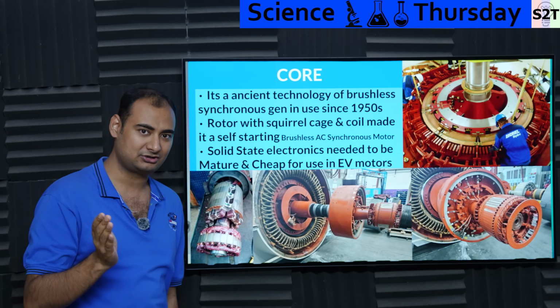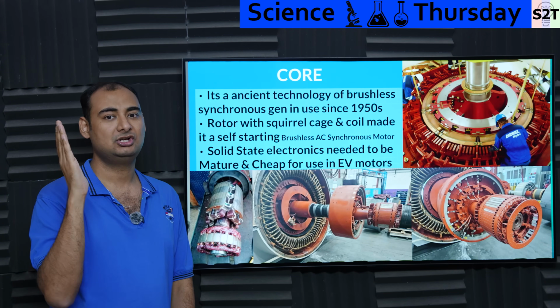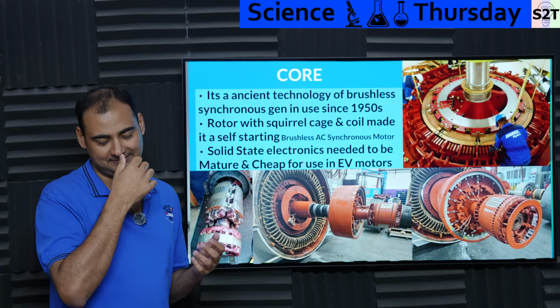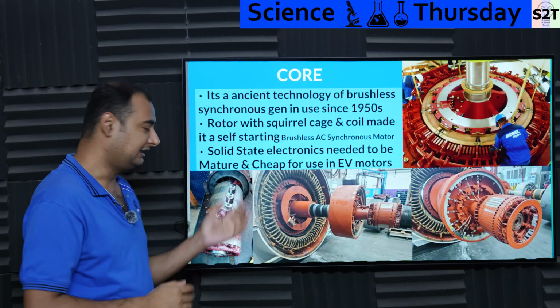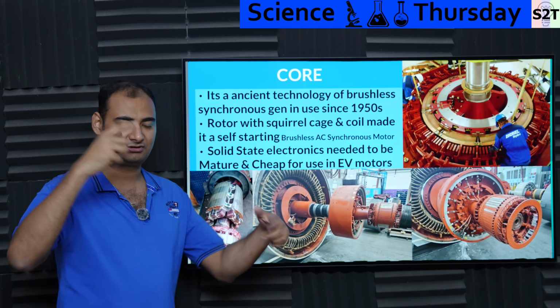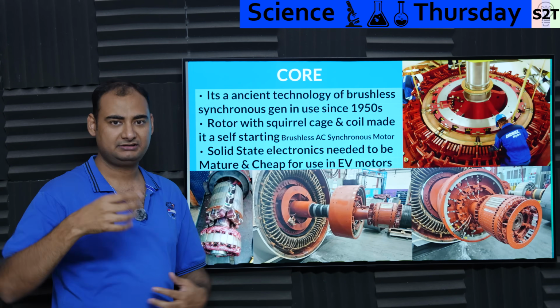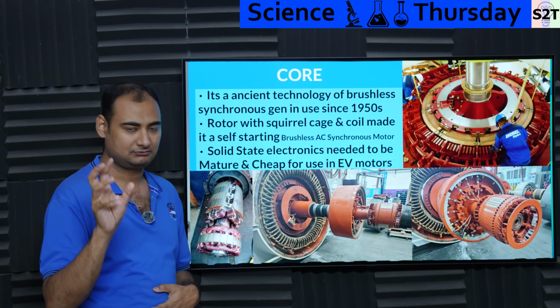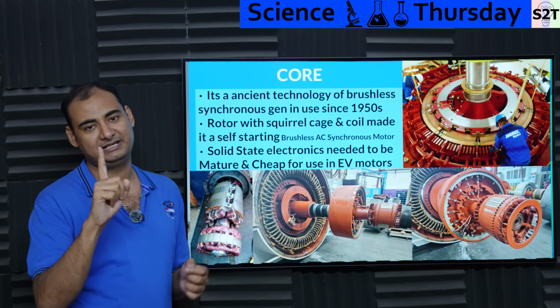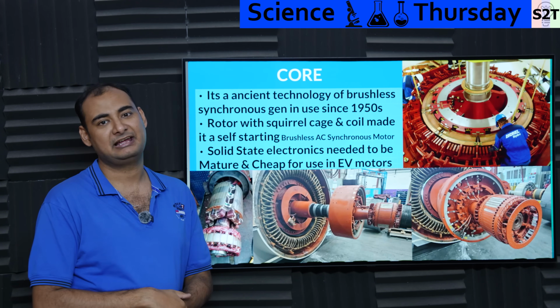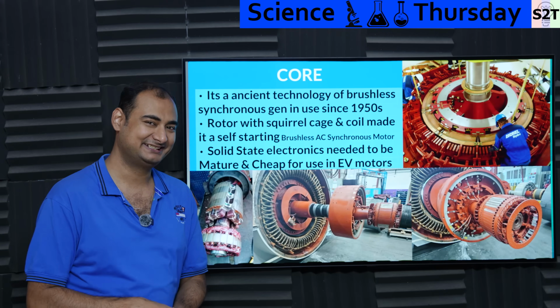Induction always needs slip in order to work. This will cancel out the slip and slowly go to lock. At that point, the squirrel cage is just dead weight. And then you can control based on the load. Let's say you're running a cement clinker, how much load is there? You can easily adjust the rotor current, and voila, the power factor will be at 1. And yes, this sort of thing has been done since the 1950s. We have been doing it.